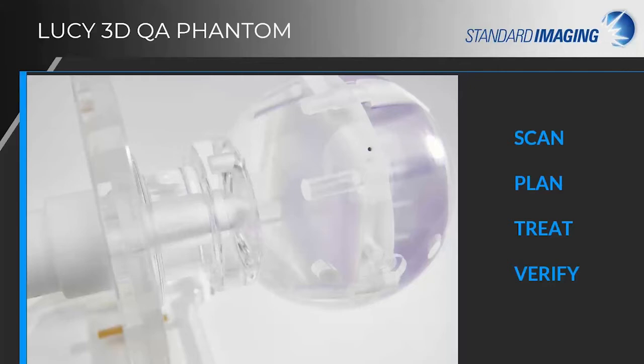So the Lucy Phantom is truly a gold standard that's been available for quite some time, used for end-to-end testing of the entire stereotactic treatment chain. The precision manufacturing of the Phantom and the inserts allows the user to verify cumulative uncertainties of the entire treatment chain to within 0.1 millimeter accuracy. This is accomplished by using a variety of inserts with precisely known volumes, geometries, and distances for accurate measurement.